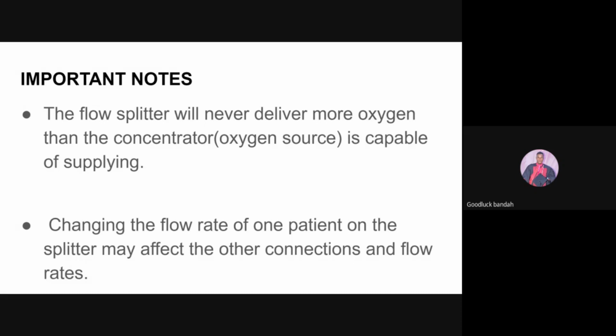When using oxygen splitters, it's important to take note of the following. The first note is that the flow splitter will never deliver more oxygen than the concentrator or the oxygen source is capable of supplying. What I mean is, if you have a source that is delivering, say, 8 liters of oxygen per minute, and you have a flow splitter that has 5 outputs, and each output is taking 2 liters per minute, you have a deficit of 2 liters per minute. In trying to cover for this deficit, you may raise the source flow rate. Consequently, you have alarms on the oxygen source of low oxygen supply. We do not want to reach this case of alarms. So always make sure that you have an oxygen source which is matching your flow splitter.